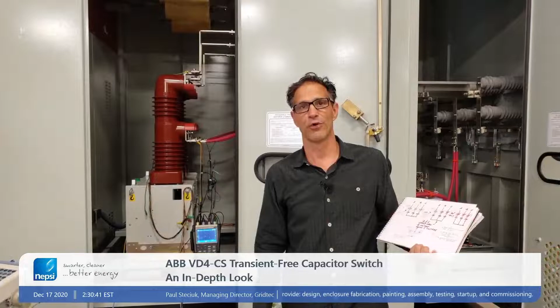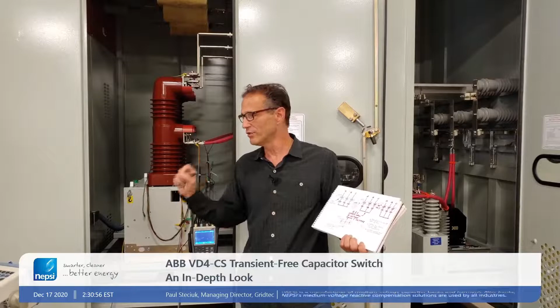Hello everyone, Paul Steciuk with Northeast Power Systems. We are continuing our evaluation of the ABB VD4-CS. It's a transient-free breaker, a transient-free switch for switching capacitor banks. This is a 20 megavar capacitor bank. We're doing an evaluation of the closing times. We want to show you how the technology works.